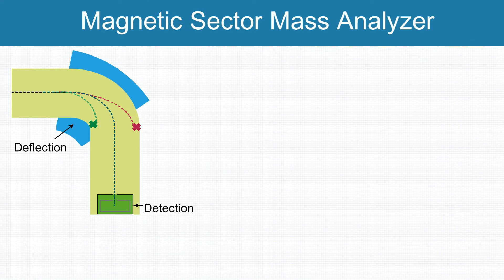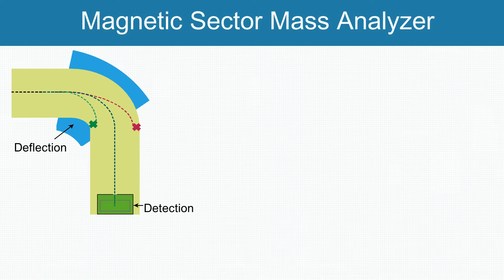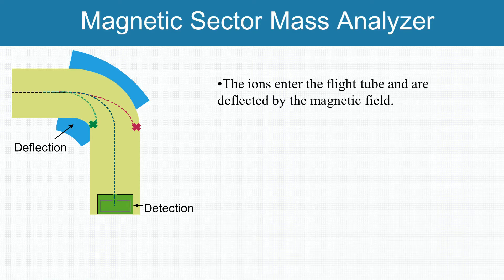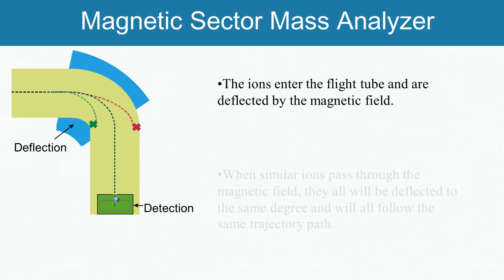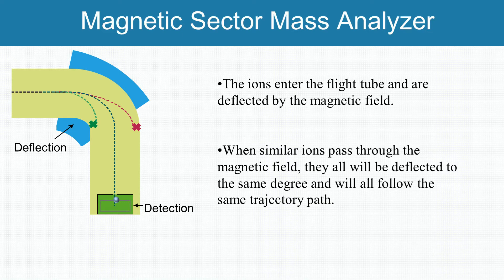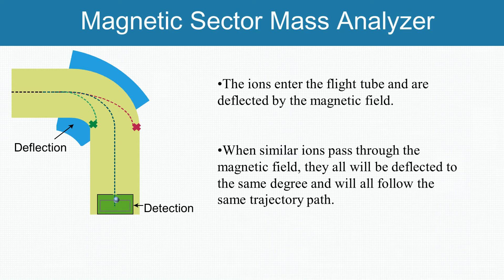In magnetic sector mass analyzer, ions are accelerated so that they have the same kinetic energy. All the ions are accelerated into a focused beam, and then the ions are deflected by the magnetic field according to masses of ions. The lighter ions have more deflection than the heavier ones. The amount of deflection depends on the number of positive charges. When similar ions pass through the magnetic field, they all will be deflected to the same degree and will all follow the same trajectory path. Those ions which are not selected will collide with either side of the flight tube wall or will not pass through the slit to the detector.